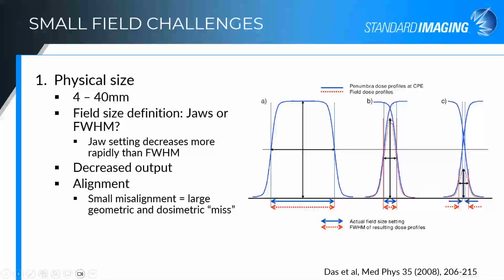And we talk about output factors decreasing as you get into these smaller fields, but the practical matter here is that because of this decrease in the magnitude of the field shape itself, the profile, this full width half max no longer lines up with the jaw sizes. And as you go to extremely small fields, that effect is greatly magnified. So that's something to keep in mind as you're defining what size field you're measuring. Actually, the full width half max matters a lot more than what you're setting for your jaw collimator settings when it comes to your detector. But when you're talking about source occlusion and those other things that are influenced by the physical position of your collimation system, then it's key to keep tabs on where your jaws are as well.